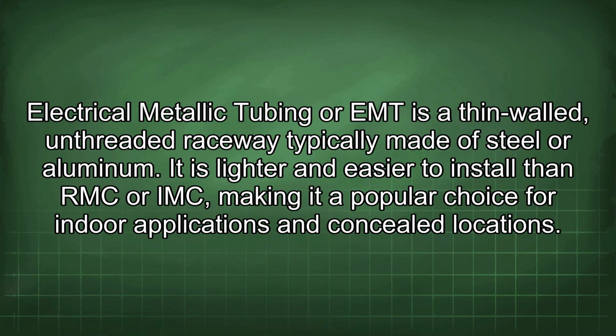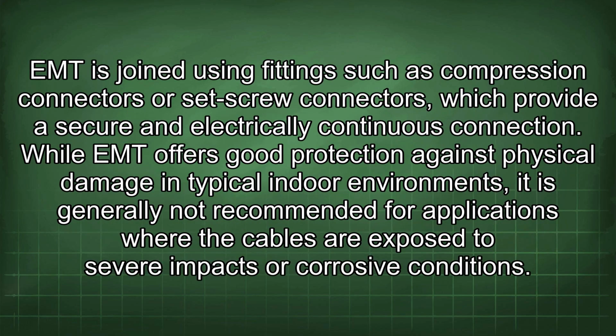Electrical metallic tubing or EMT is a thin-walled, unthreaded raceway typically made of steel or aluminum. It is lighter and easier to install than RMC or IMC, making it a popular choice for indoor applications and concealed locations. EMT is joined using fittings such as compression connectors or set screw connectors, which provide a secure and electrically continuous connection. While EMT offers good protection against physical damage in typical indoor environments, it is generally not recommended for applications where the cables are exposed to severe impacts or corrosive conditions.